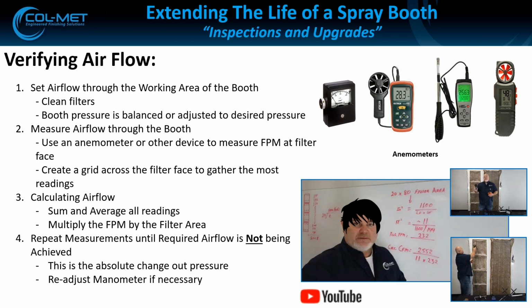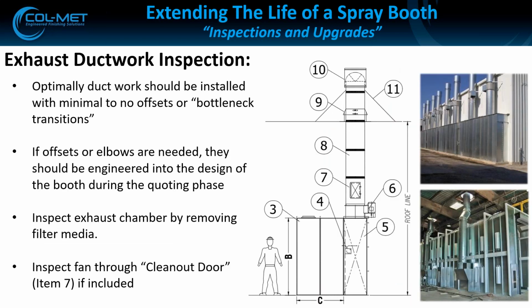Moving through airflow, what I like to do is measure it at the filter face. I feel that's the most accurate way, because all the air going out of the booth goes through the filter face. Then you just calculate that airflow, and you want to repeat these measurements until you're no longer seeing the target achieved. That's when you're setting a manometer. Or when you're doing booth inspections, if we're not achieving those 100 feet per minute with clean filters, then we've got to start digging a little deeper and looking into other items.